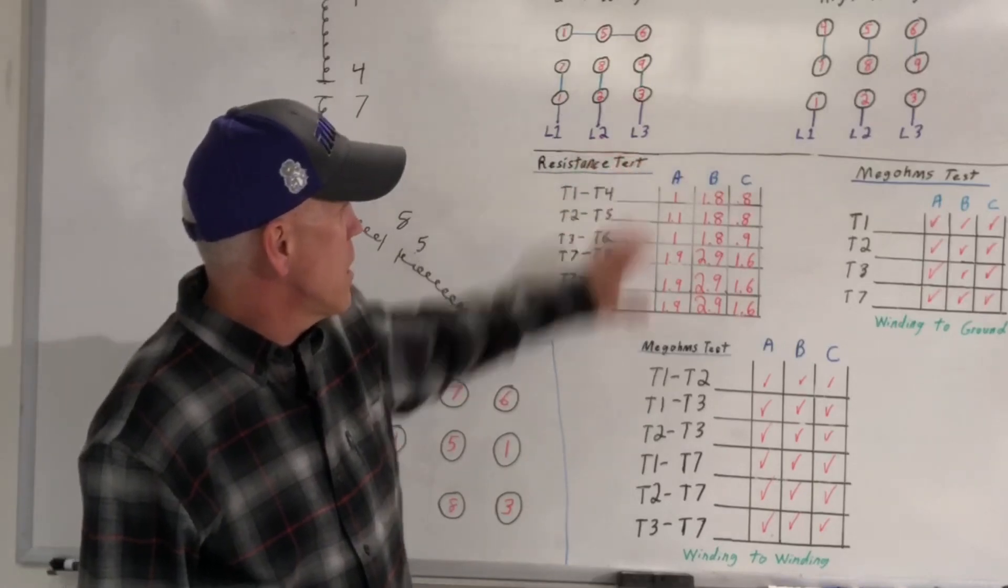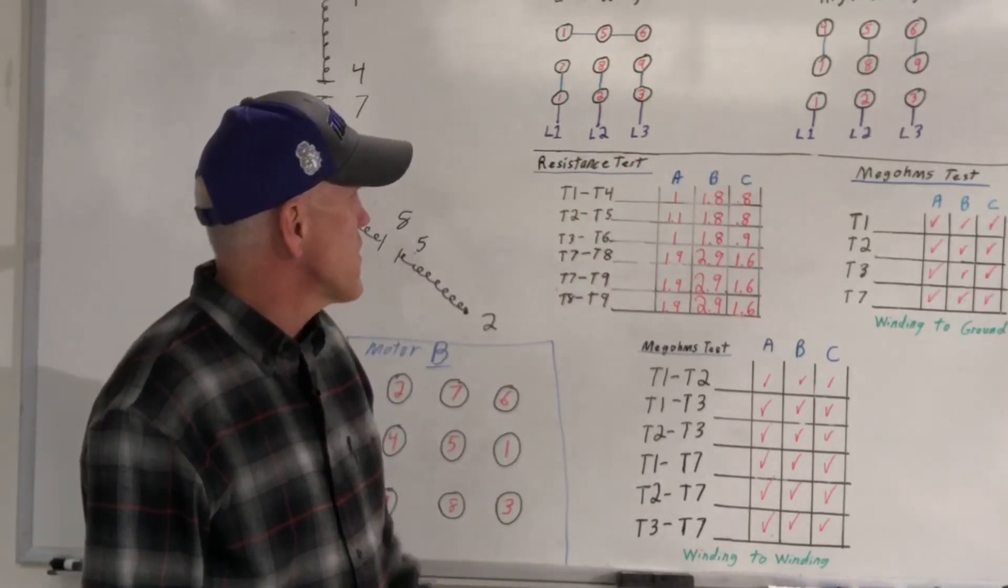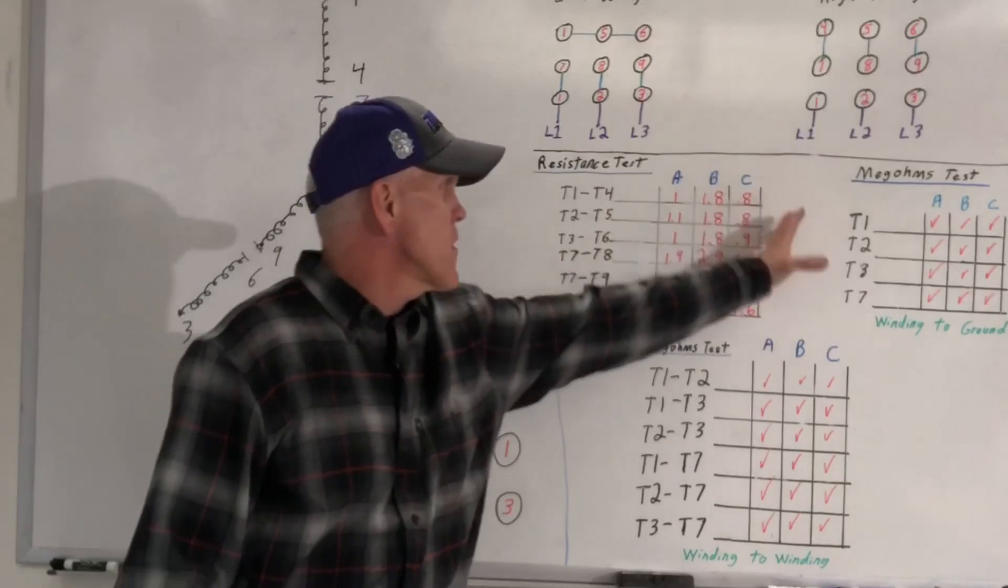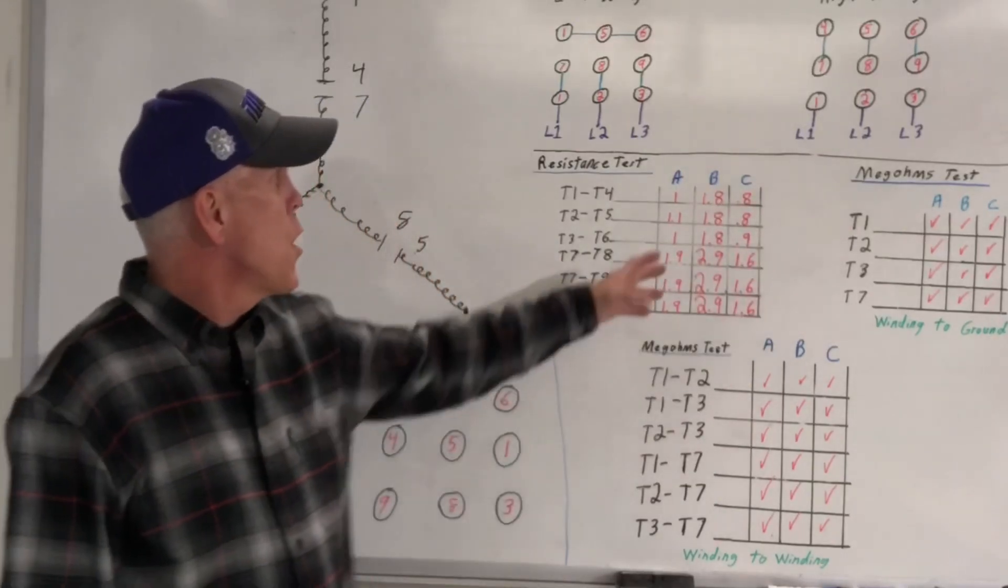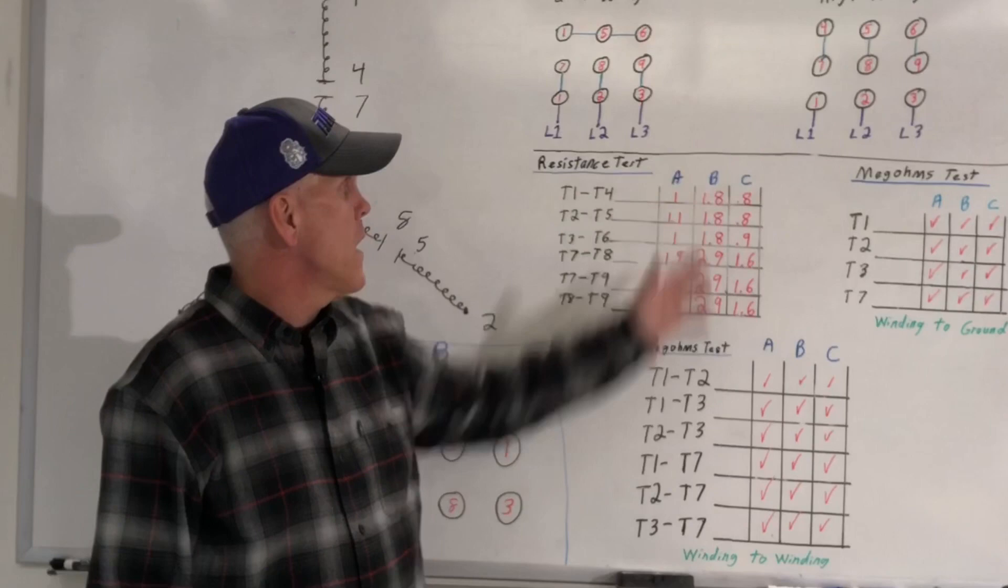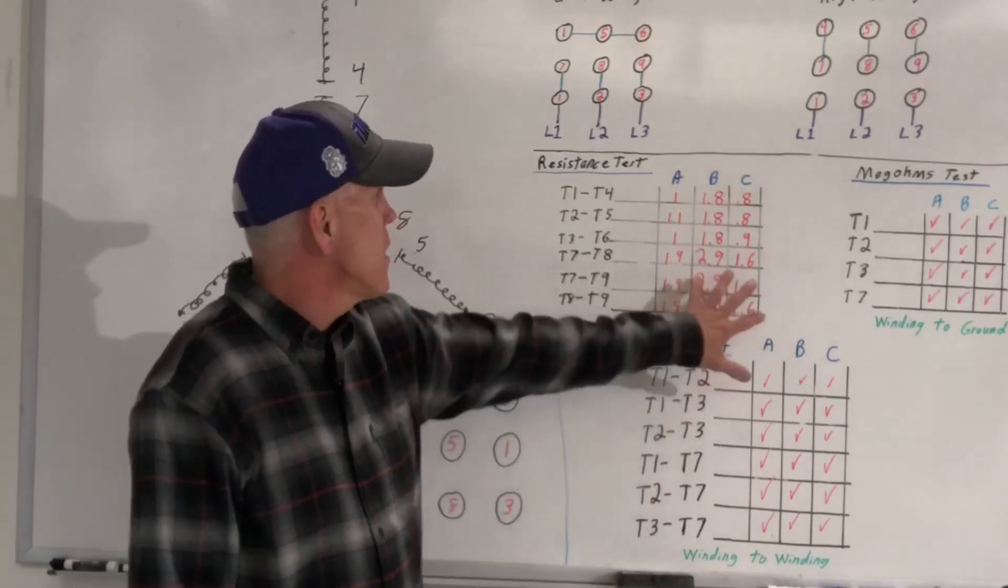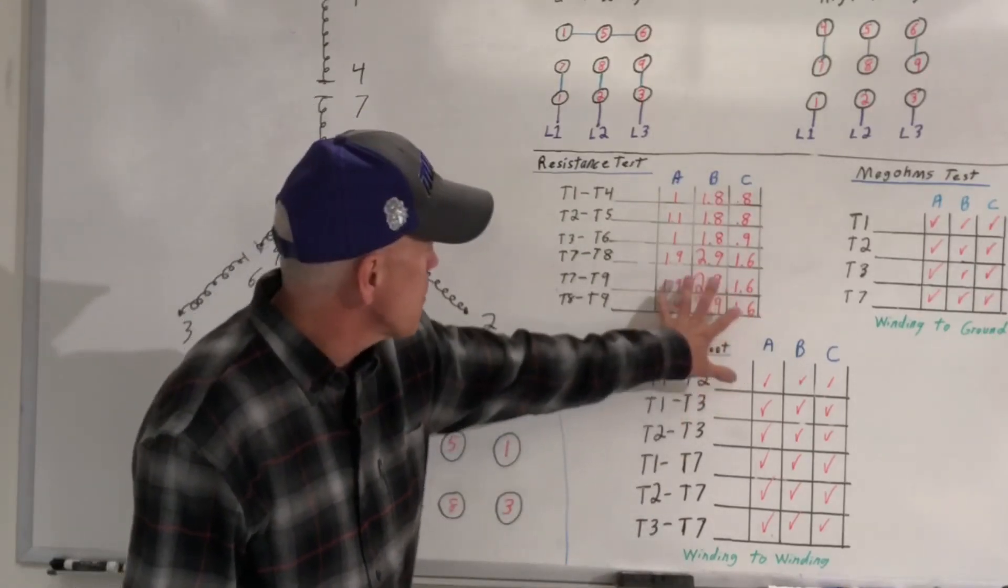Motor A, all the resistance tests look good on that. Motor C resistance test looks good on that. Motor B, the resistance test on that was higher than the other two motors. The other two motors within range.